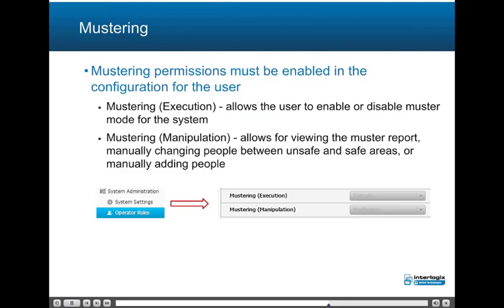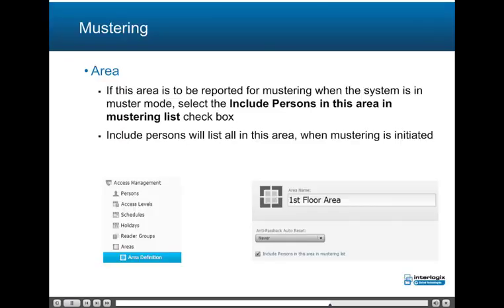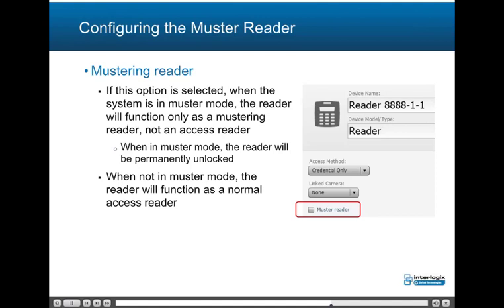Mustering permissions must be enabled in the configuration for the user. Mustering execution allows the user to enable or disable muster mode for the system. Mustering manipulation allows for viewing the muster report, manually changing people between unsafe and safe areas, or manually adding people to the mustering or dangerous location. If a specific area is to be reported for mustering when the system is in muster mode, the 'Include Persons in this area in mustering list' checkbox must be selected. The Mustering Reader option, if selected on the reader configuration, when the system is in muster mode, the reader will function only as a mustering reader, not an access reader; when in muster mode the reader will be permanently unlocked. When not in muster mode, the reader will function as a normal access reader.